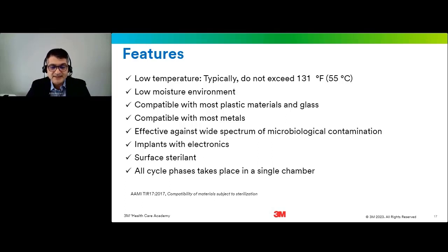It is effective against a wide spectrum of microbial contamination. It can be used for sterilization of implants with electronic components that are heat and moisture sensitive, that they cannot tolerate steam. It is a surface sterilant and does not penetrate through materials. So this can be useful. Let's have an example here. If there's a syringe filled with a sensitive medication that you don't want a sterilizing agent to reach, this sterilant only sterilizes the outside surface of that syringe and does not penetrate inside.